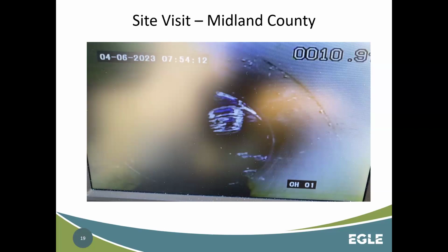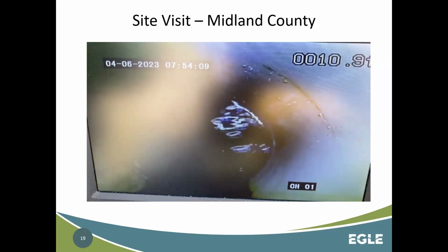They had tried a number of different things, like disinfection and replacing the pressure tank, and nothing was really working. Well, Kathy and I showed up on site, and we took the well cap off, and we looked down into the well to see where the static was, and you could see this waterfall effect on the water itself, and we knew something was wrong already. I'll show that again.